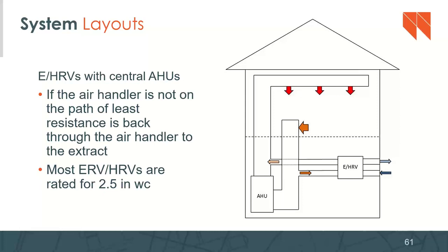Here is a slight change to trying to hook this ERV, HRV up to the air handler return side. What you could do instead is have the supply air going to either the supply air of the air handler, or sometimes you can have it go to the return air of the air handler as well. But in this case, you're sending fresh outside air to the supply air of the air handler and it's being distributed through the heating and cooling ductwork to the spaces in the home, while at the same time you're exhausting the return air, that's your supply of stale indoor air being brought out of the building. That's an option that you could do.